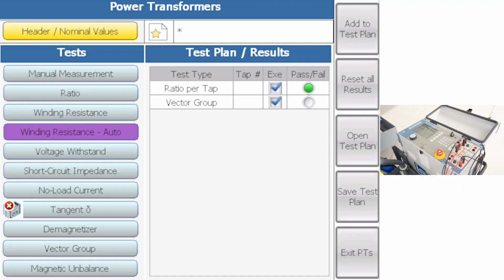Let's do the winding resistance test. First, let me explain the connections on the STS. So what are we doing here? We are generating from the 6 amp output. Of course, 6 amp is the maximum here. You can generate any other current which is lower. And by the way, let me say that we also have another output through which we can generate up to 100 amp DC, but in this case we are using this output.